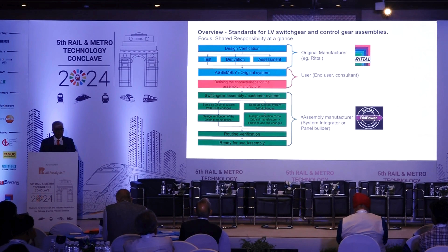I'd like to develop on this a bit more. What solutions do we have? We have solutions in copper as well as aluminum. We can go up to a tested system of up to 6300 amps, with IP up to IP54, and a short circuit current rating of 100 kA for 1 second. The enclosures can comply up to zone 5. So the standard we follow is IEC 61439, Part 1 and Part 2.